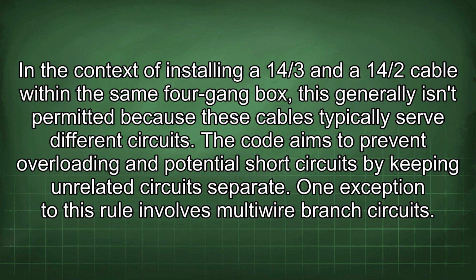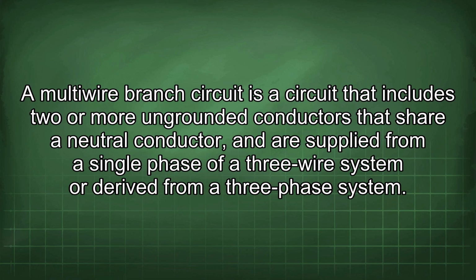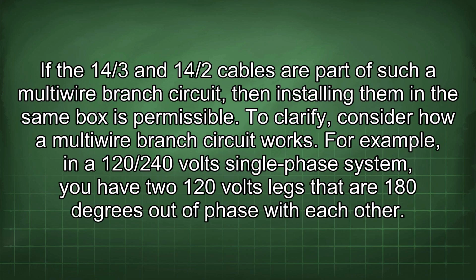One exception to this rule involves multiwire branch circuits. A multiwire branch circuit is a circuit that includes 2 or more ungrounded conductors that share a neutral conductor and are supplied from a single phase of a 3-wire system or derived from a 3-phase system. If the 14/3 and 14/2 cables are part of such a multiwire branch circuit, then installing them in the same box is permissible. To clarify, consider how a multiwire branch circuit works.